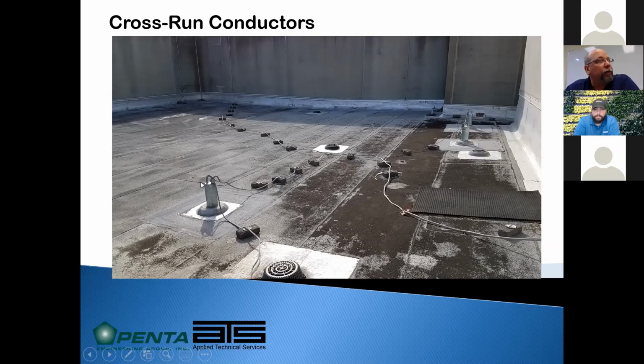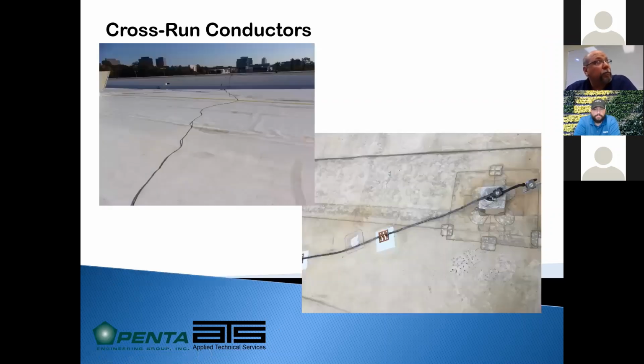If they're tying a rope to that anchor, we have sharp edges that could cut that rope. So we would have a clamp around the bottom. This would be installed, all the conductor would be installed in a neat professional manner, going in more straight lines and securely fastened to the roof using sacrificial pads, basically little small squares of the roofing material that the roofer would install, let us install that. And with TPO or PVC type membranes, we still need the cross-run conductor secured every 3 feet. Depending on the manufacturer of the roof, some manufacturers will let us adhere the cable hold down clips directly to the roof surface. Some require these sacrificial pads.